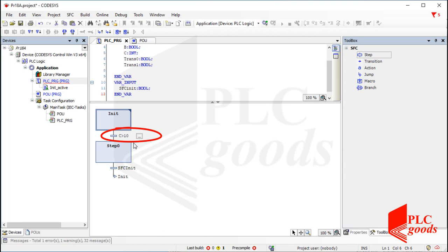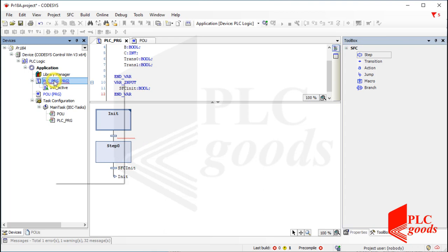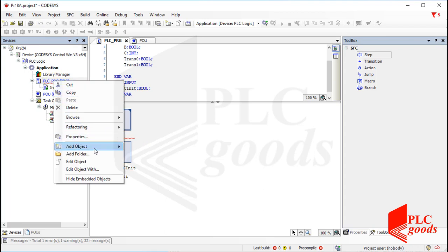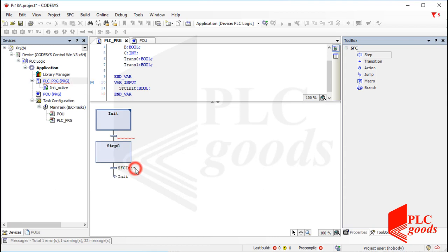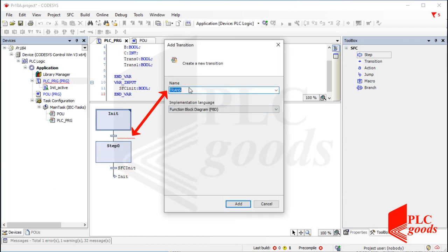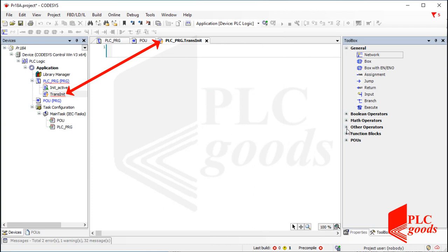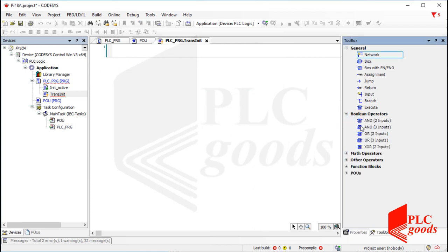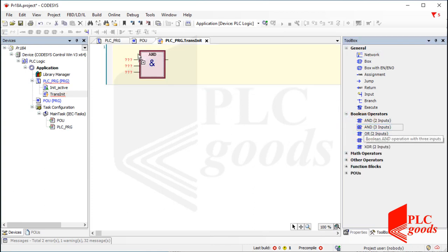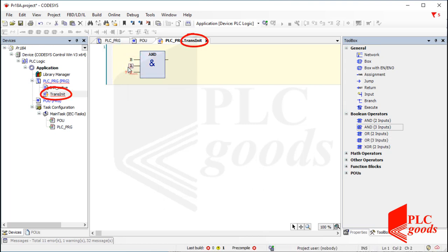As you see, I can directly write simple conditions in structured text, but if you need to write a more complex condition, or you want to use another language, a transition should be defined, and then called like actions. Note that the selected name for the transition will be used as its output. Alright, let me write a simple program. Pay attention, the result of conditions must return a Boolean variable. As I've mentioned before, the name of the transition should be used as its output variable.